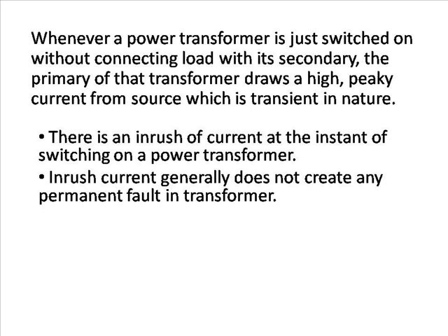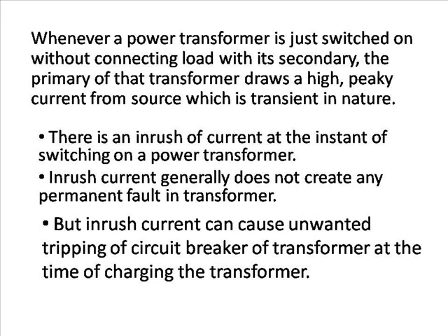Since the duration of this current is up to a few milliseconds, inrush current generally does not create any permanent fault in the transformer. But inrush current can cause unwanted tripping of the circuit breaker of the transformer at the time of charging the transformer. Let's have a look at the basic theory of inrush current in a transformer. Not only in transformers, in all devices where a magnetic core is used, the phenomenon of inrush current may happen.